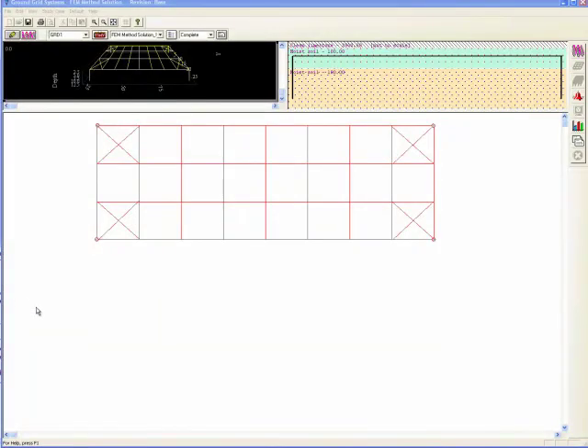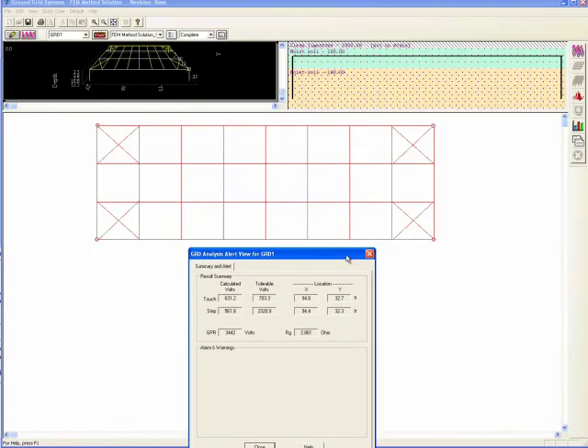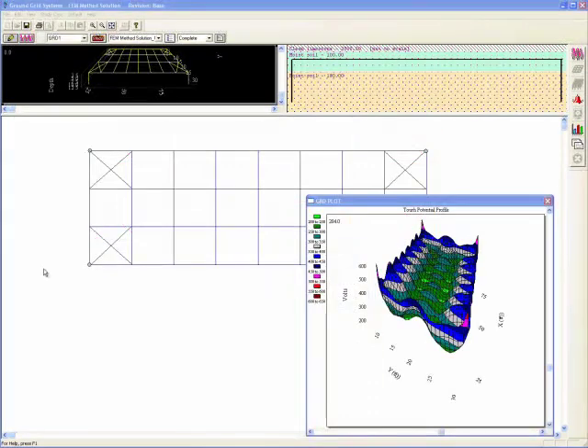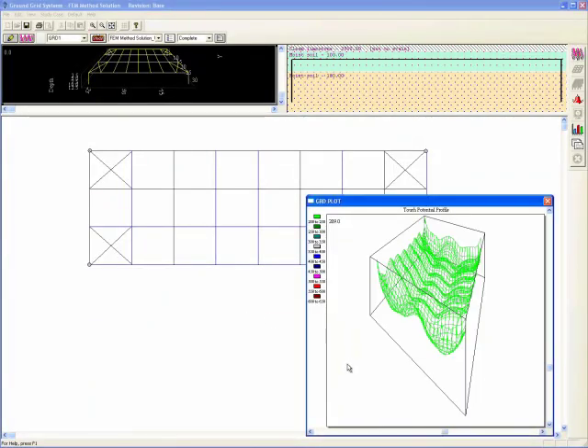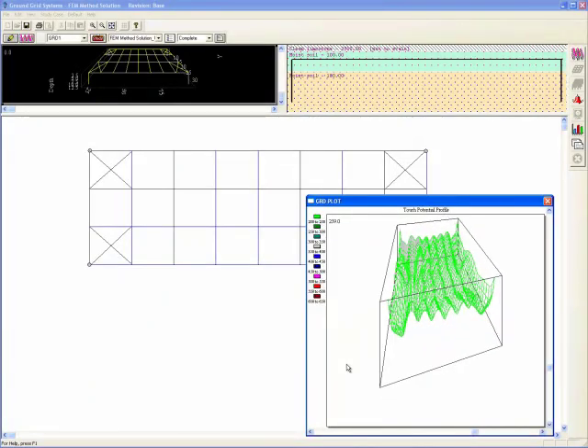As a solution with the finite element modeling, an engineer may now choose to use 4 sets of crossing conductors at the grid corners, which reduce the touch voltage by almost 13% and simply resolve the issue. The touch voltage drop of the grid corners can be observed through the plot as well.